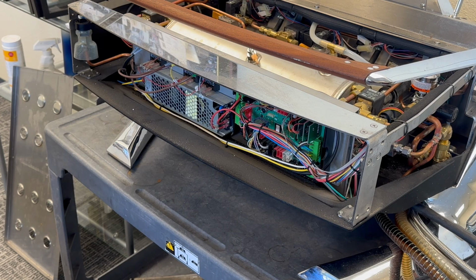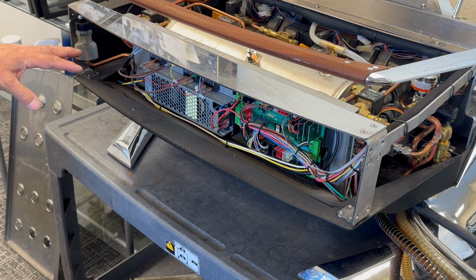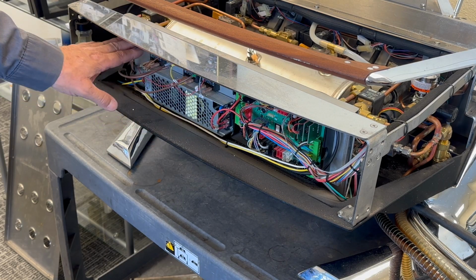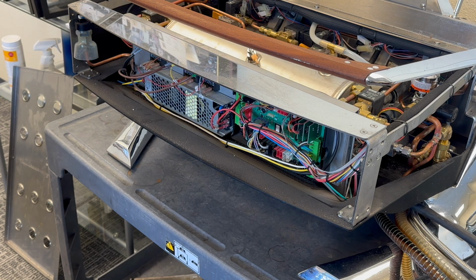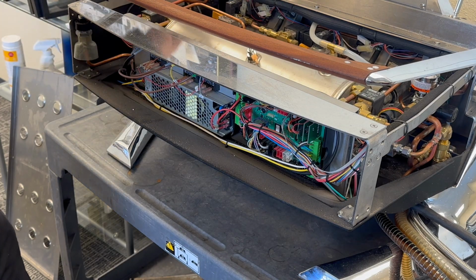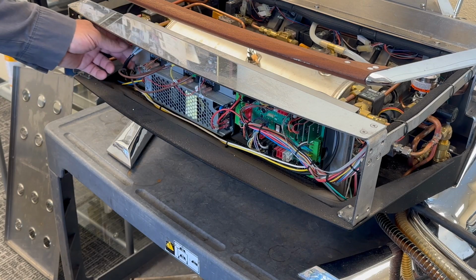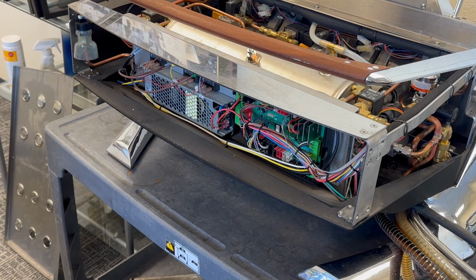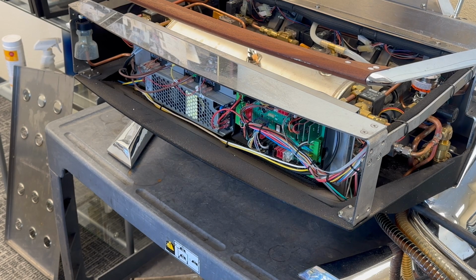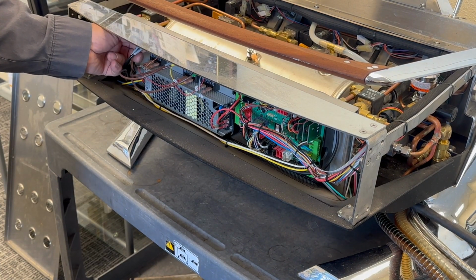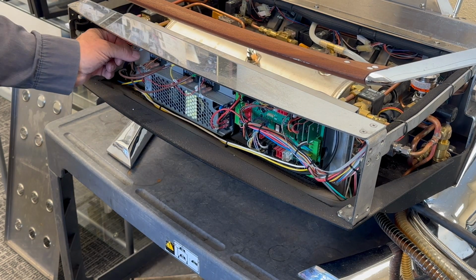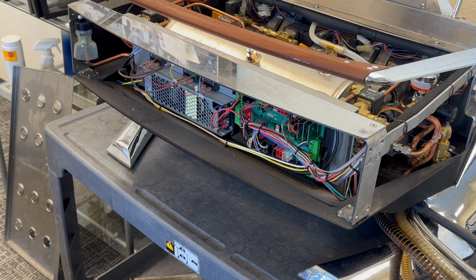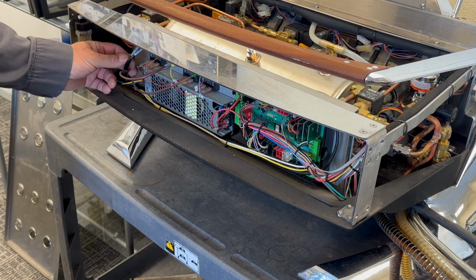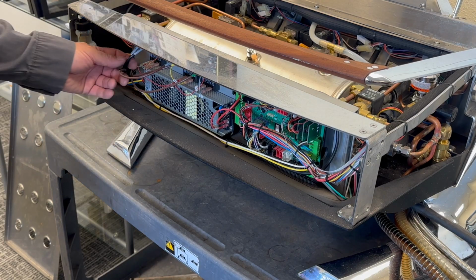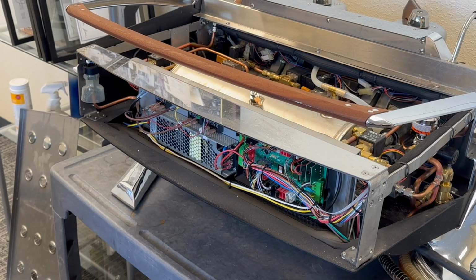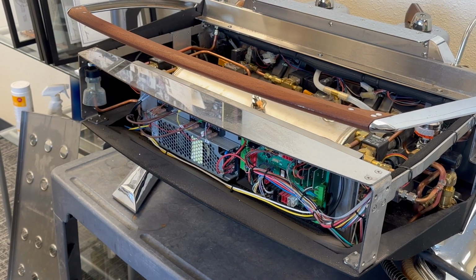Would you check the terminals? I would generally, especially our high voltage wire connections on our solid state relays, inspect those yearly. Usually you'll see problems up at the heating elements, and the wire terminals getting discolored, and the plastic when it gets super hot will start to get brittle. The wire coating will also become brittle. You can feel the heat off a wire while it's heating, and if it's super hot, there's usually a connection problem somewhere - it could be back here, at the elements, or at the terminal block.